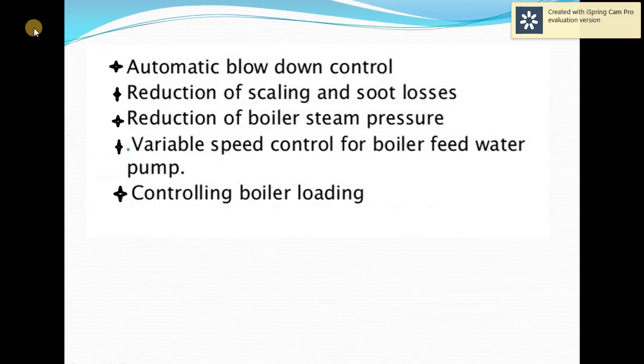Additional energy saving points for boilers include: reduction of boiler steam pressure, variable speed control for the boiler feed water pump, and controlling boiler loading. Using these techniques and methods, we can save energy while generating steam in the boiler.